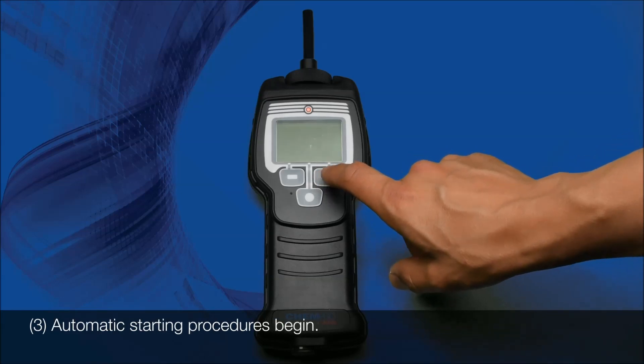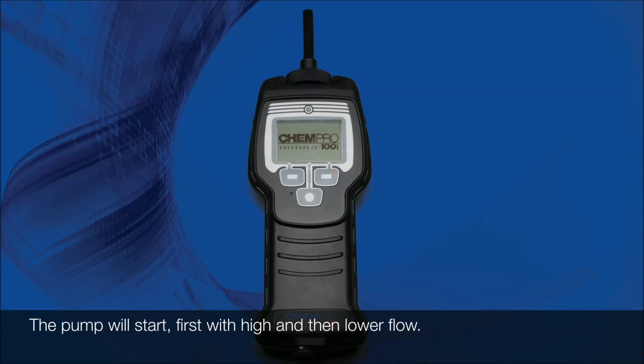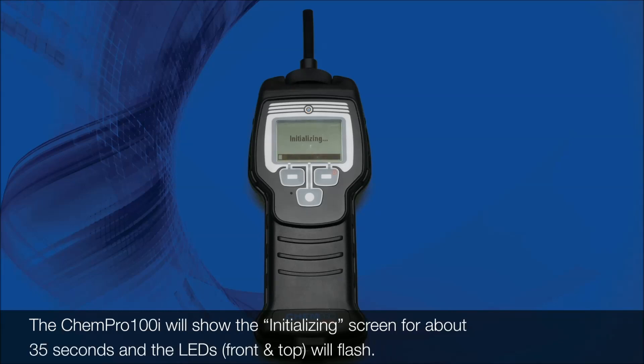Step 3: Automatic starting procedures begin. The backlight will come on and the display will show the ChemPro100i logo for about 5 seconds. The pump will start, first with high and then lower flow. The ChemPro100i will show the screen for about 35 seconds and the LEDs will flash.